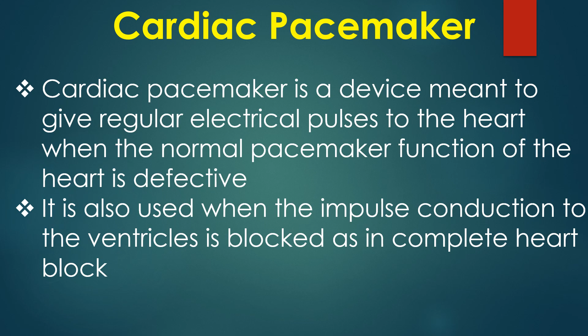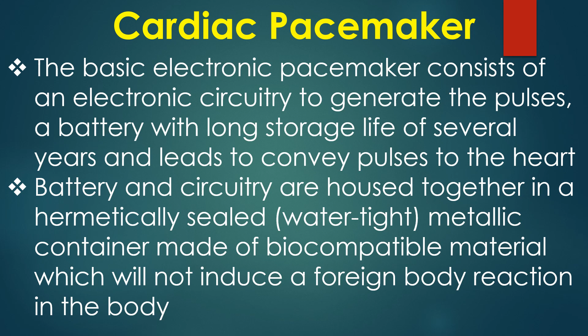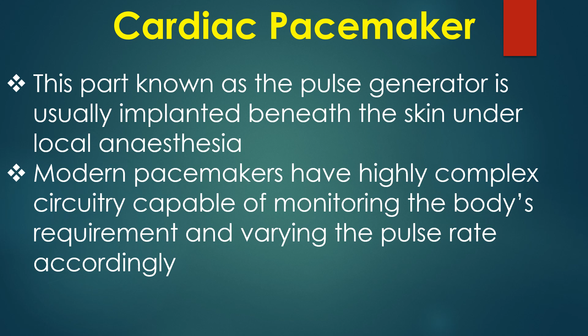Battery and circuitry are housed together in a hermetically sealed metallic container made of biocompatible material which will not induce a foreign body reaction in the body. This part, known as the pulse generator, is usually implanted beneath the skin under local anesthesia. Modern pacemakers have highly complex circuitry capable of monitoring the body's requirement and varying the pulse rate accordingly. They are also communicating devices which can transmit the stored information to a device known as programmer kept over the surface of the skin.